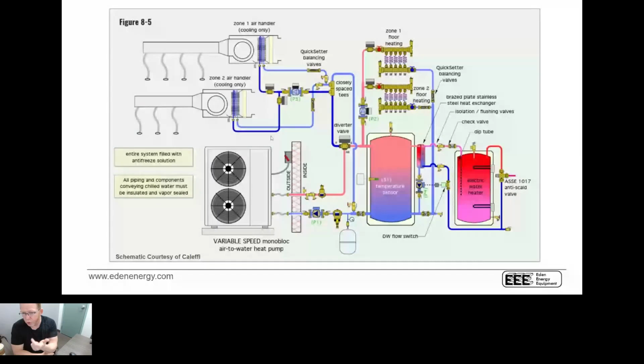So where we were talking about comfort, if we're not going into a radiant slab where it's 66 degrees, we're actually going out to the air handler. We want to have water temperature as cold as possible, getting it down to 47, 46 degrees. Well, if we feed it into the tank, there's potential for mixing. So the diverting 3-way valve allows us to deliver the chilled water directly to the air handlers because we're not typically going to have microzones.